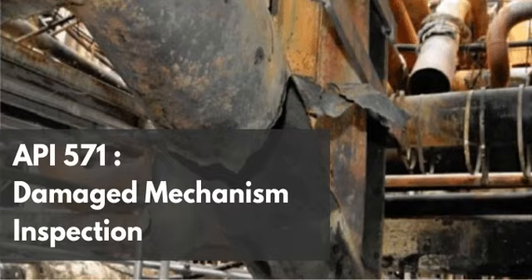Man. So you have a susceptible copper alloy, and you have artificially injected a massive amount of residual stress via the rolling process. Right. And if the cooling water or the process fluid happens to contain ammonia, it's just a matter of time. The triad is complete. The transgranular or intergranular cracks will almost always initiate right at that high-stress rolled transition.